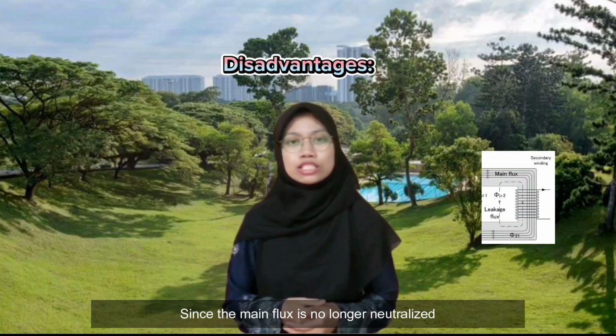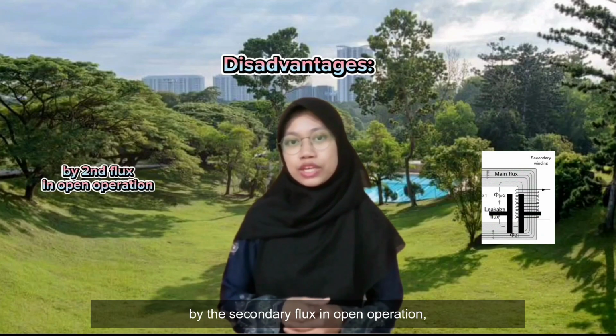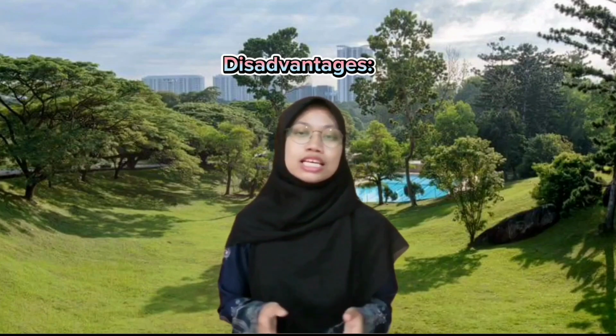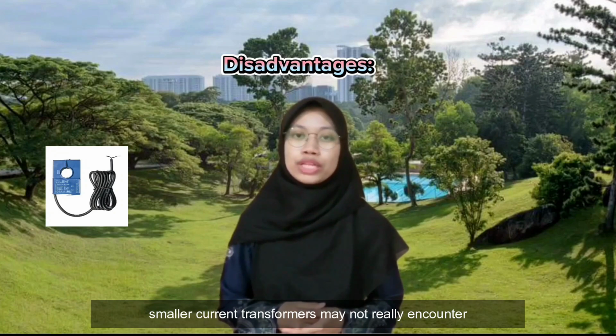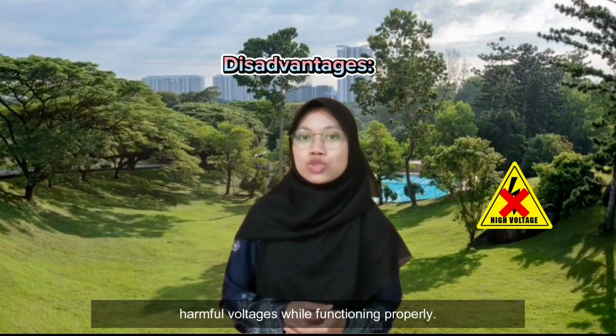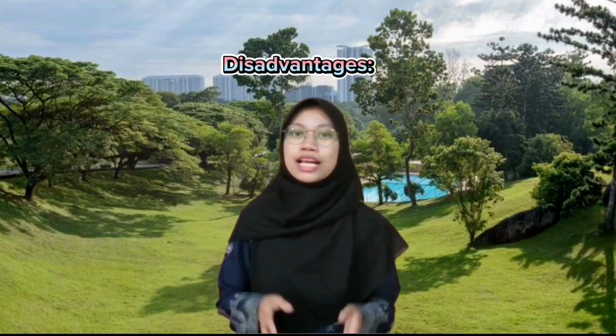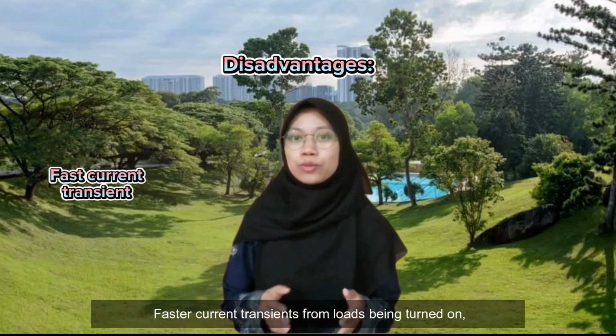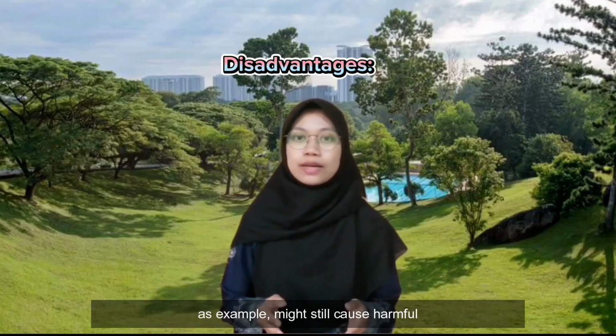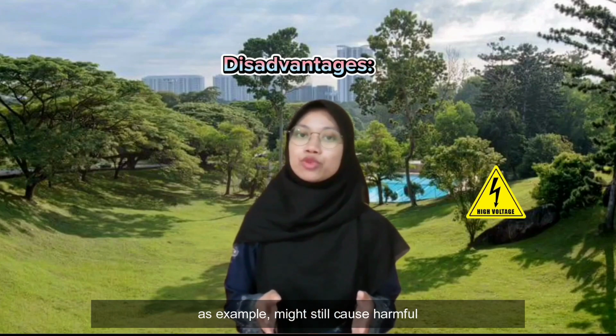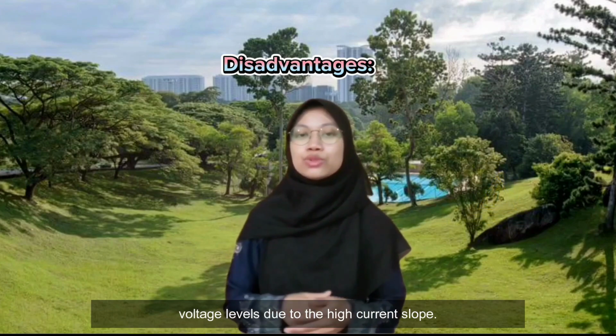Since the main flux is no longer neutralized by the secondary flux in open operation, smaller current transformers may not really encounter harmful voltages while functioning properly. Faster current transients from loads being turned on, for example, might still cause harmful voltage levels due to the high current slope.